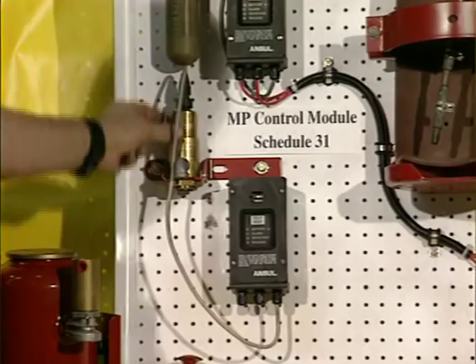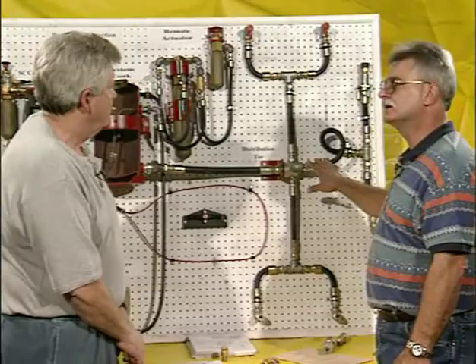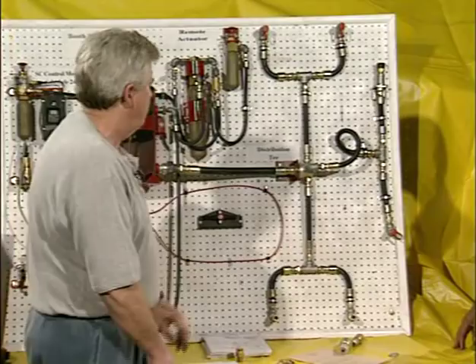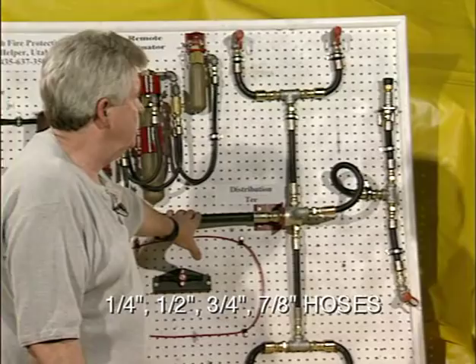For the distribution system on the Ansul system, the supply line can be either three-quarter or seven-eighths inch — that's what the Ansul specs require. Secondary piping is half-inch. The only other size used would be quarter-inch for the nitrogen firing system. The supply lines from the tank to the distribution T are always seven-eighths or three-quarter. Note that a street elbow cannot be used because it isn't listed or approved in any of the distribution systems.